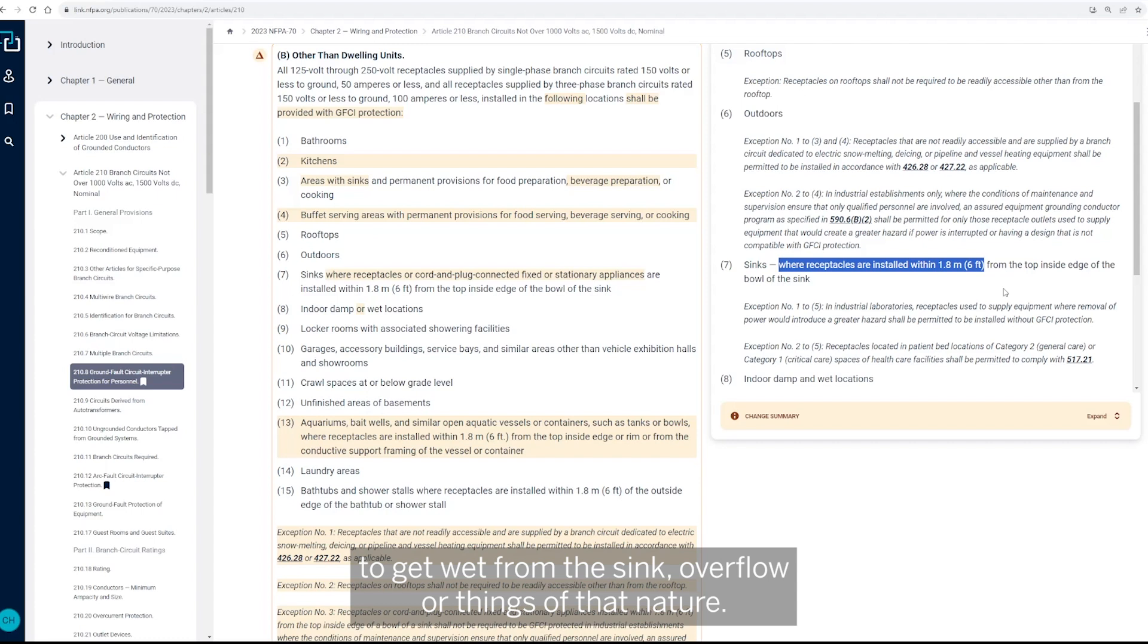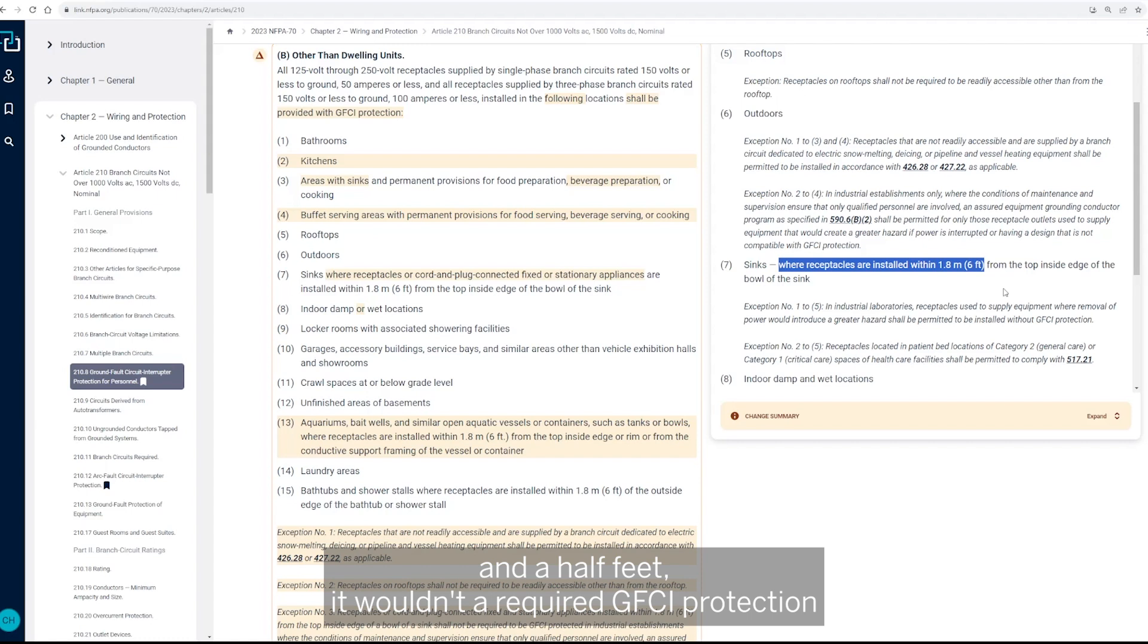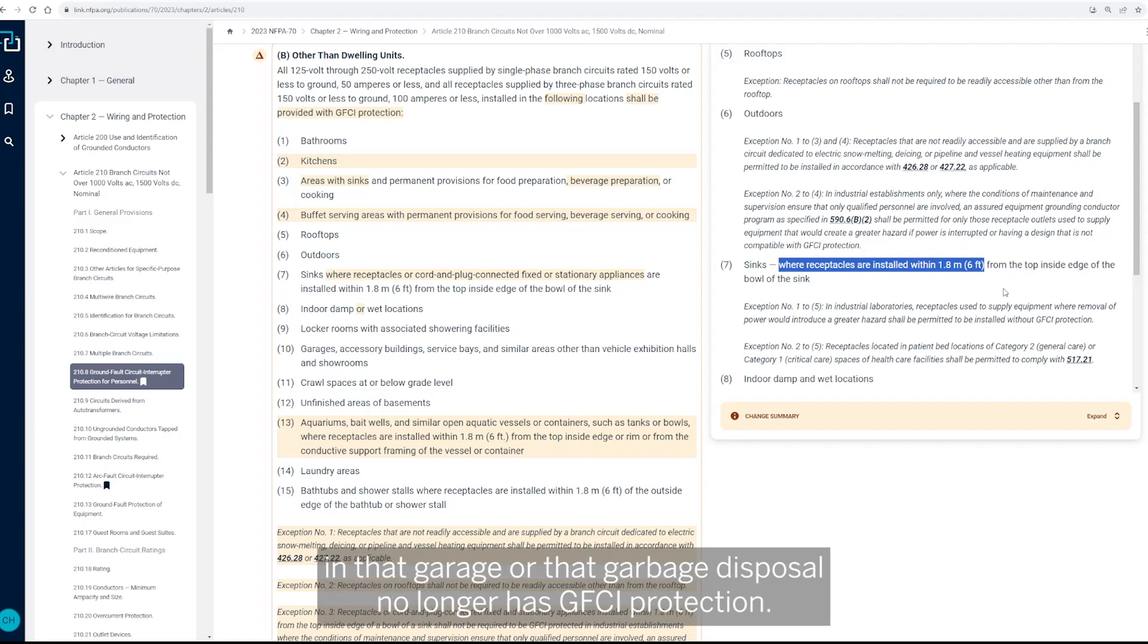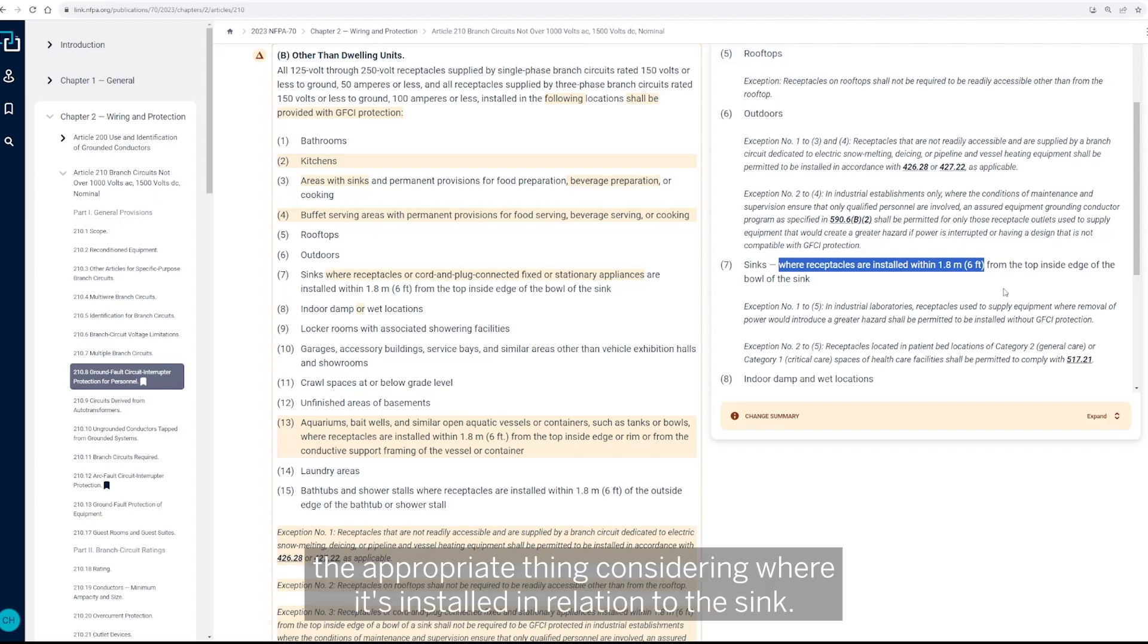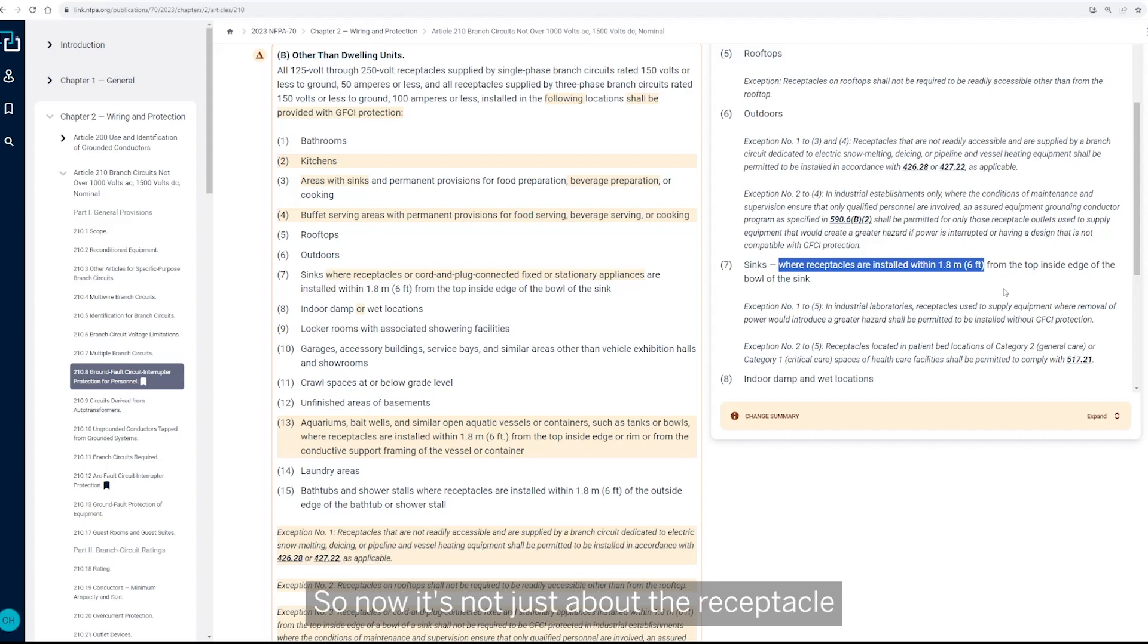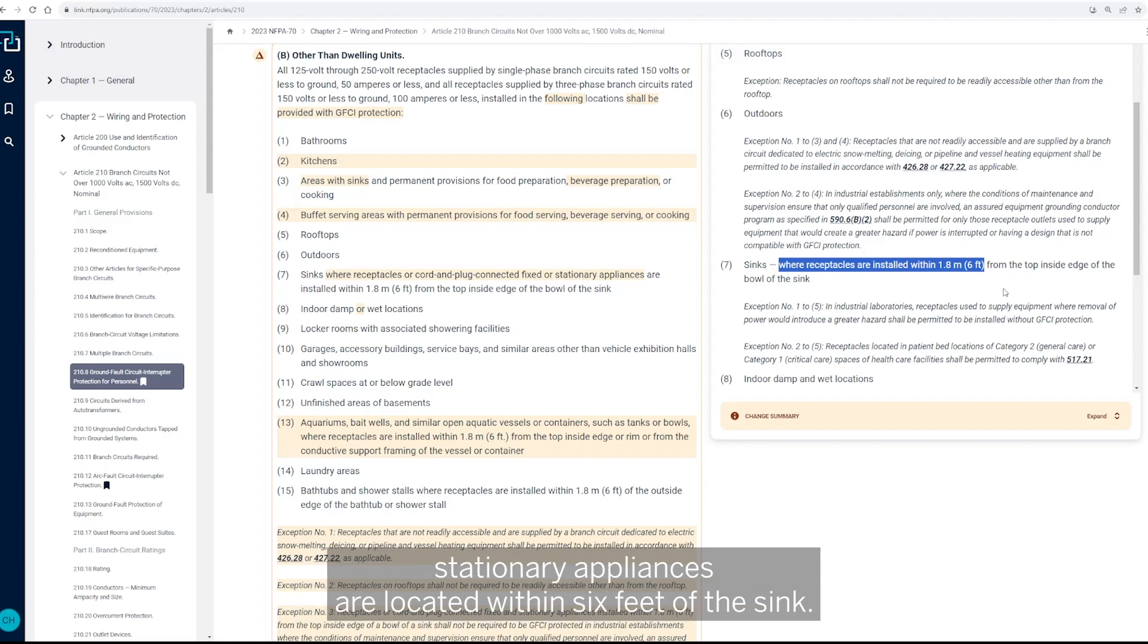So now because the receptacle was at six and a half feet, it wouldn't require GFCI protection, and that garbage disposal no longer has GFCI protection that would seem to be the appropriate thing, considering where it's installed in relation to the sink. So now it's not just about the receptacle location, but also where any cord and plug connected fixture stationary appliances are located within six feet of the sink.